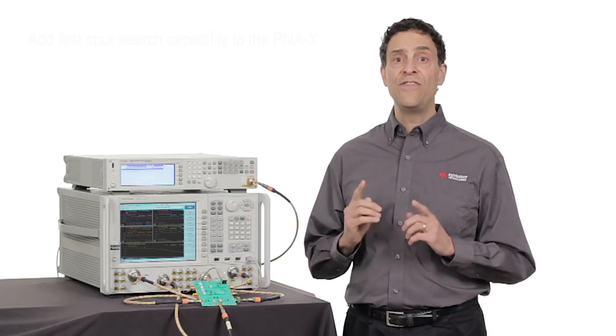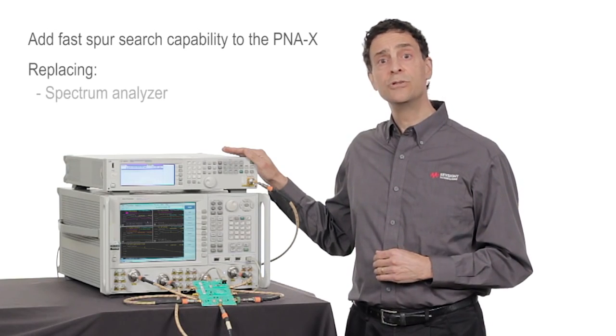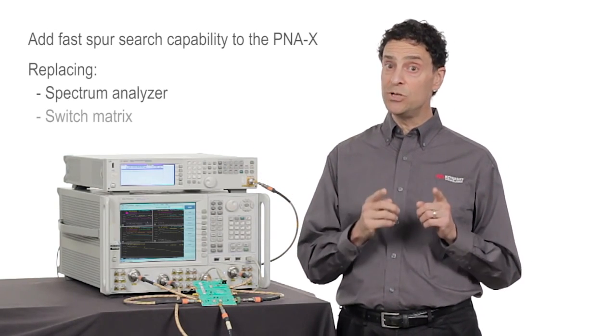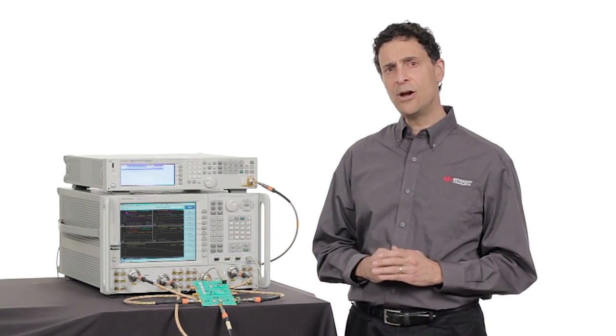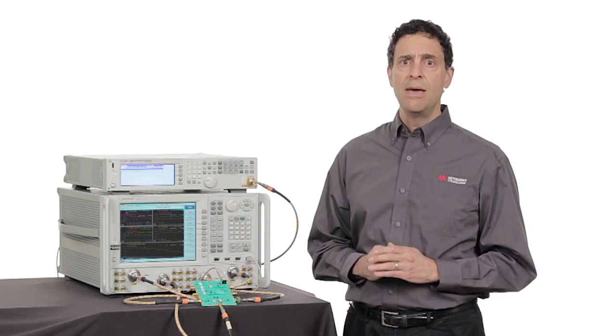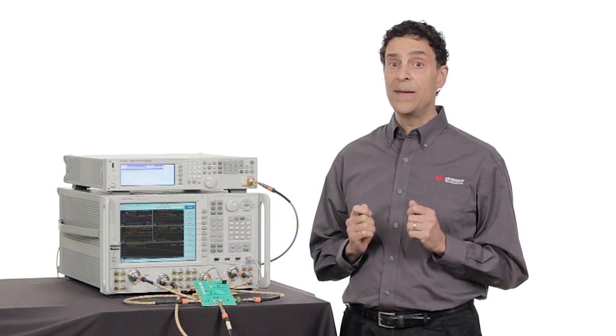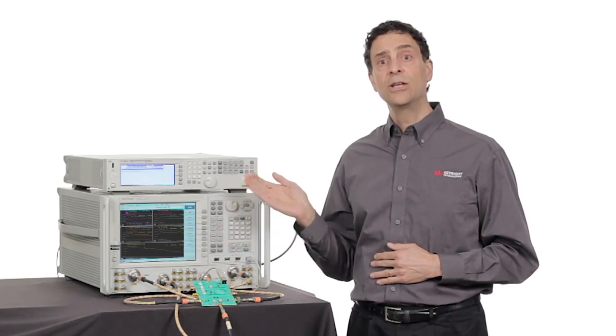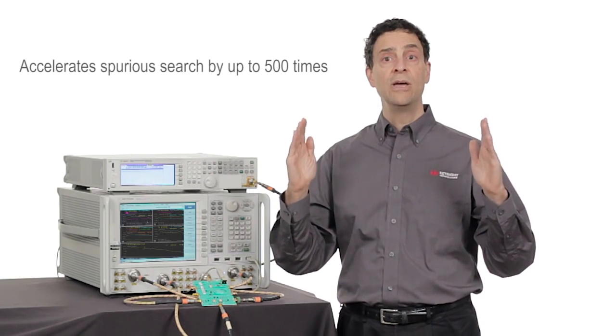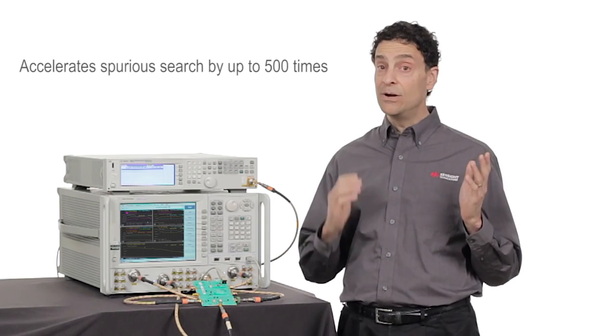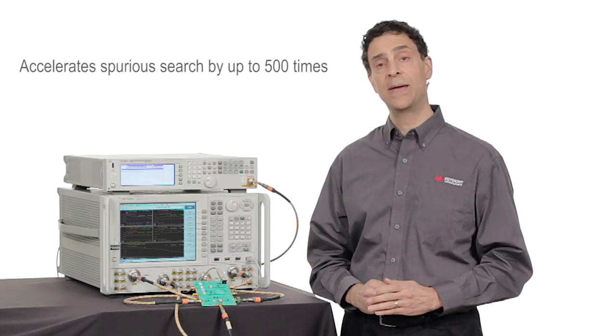The new PNA option adds fast spur search capability to the PNA-X, replacing a stand-alone spectrum analyzer, converter, and switch matrix in your test systems. Spurious measurements are a very important part of characterizing frequency converters, but they often take a great deal of time. With the new spectrum analyzer option, a PNA-X can quickly perform spurious searches across a broad frequency range, with measurements that are as fast or often faster than those from today's best stand-alone spectrum analyzers.